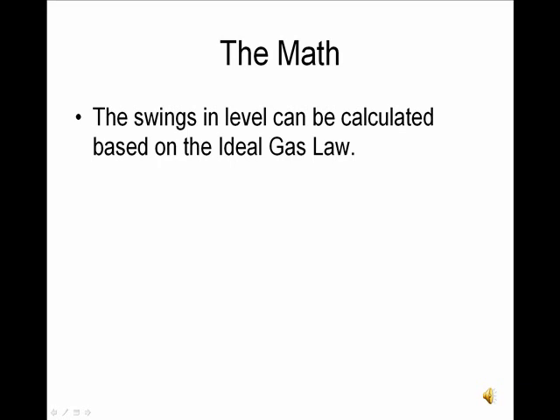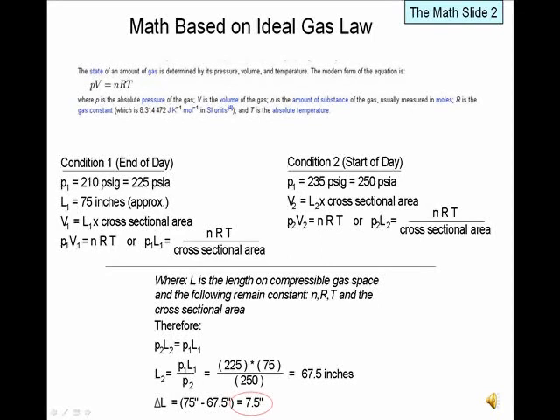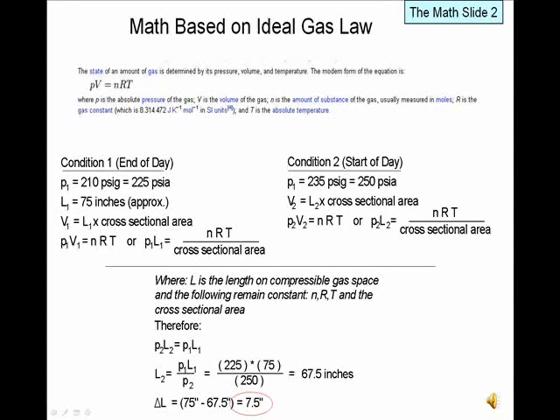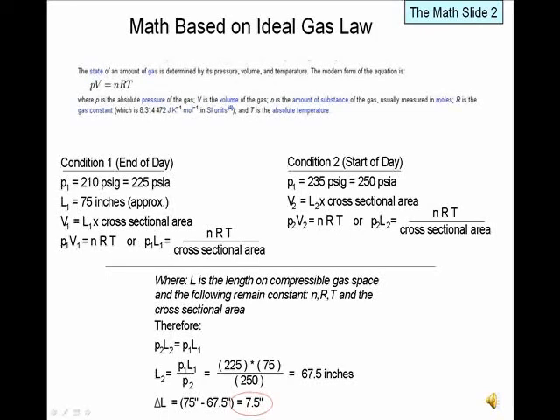The swings in level or drift can be calculated based on the ideal gas law. This slide highlights the compressible gas section on the high phase line; for our calculation, this length will be known as L. The ideal gas law states the amount of gas is determined by its pressure, volume, and temperature, represented with the equation PV = nRT. We can use this relationship to determine the change in compressible gas space in the high phase line. In our example, nR and T are constant; therefore, the starting and ending conditions must follow P1 × V1 = P2 × V2. We know the starting and ending pressures, and the volume can be related to the length of the phase line.